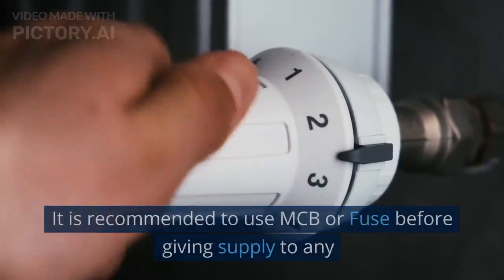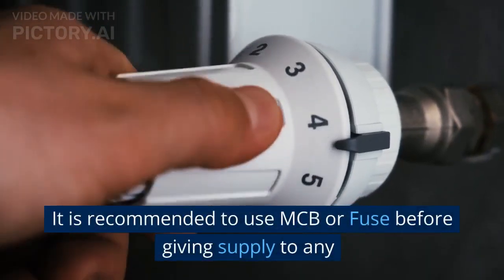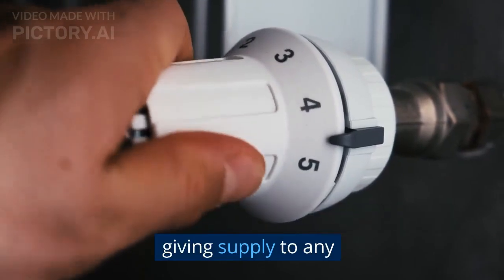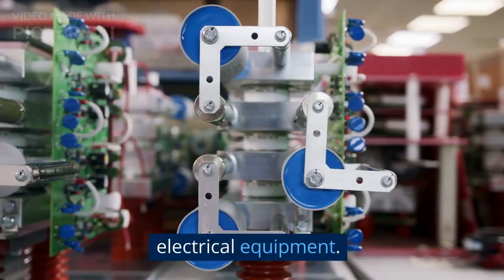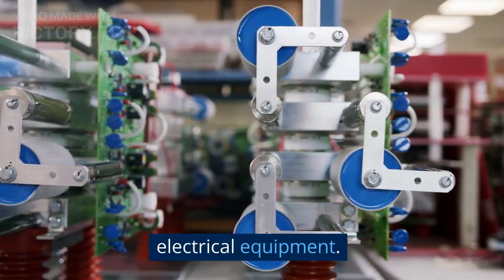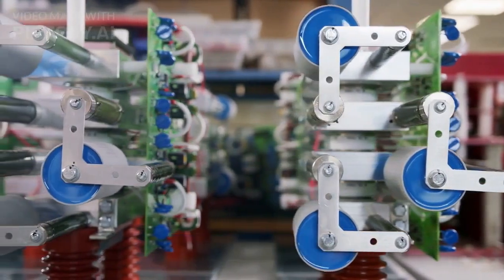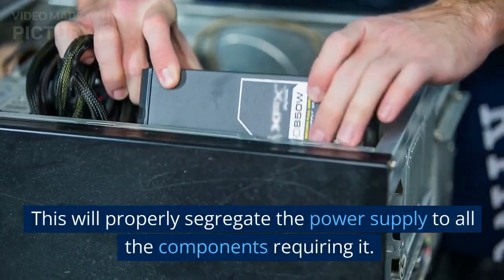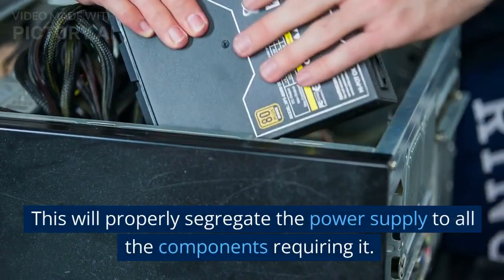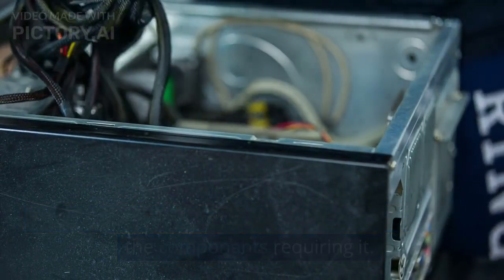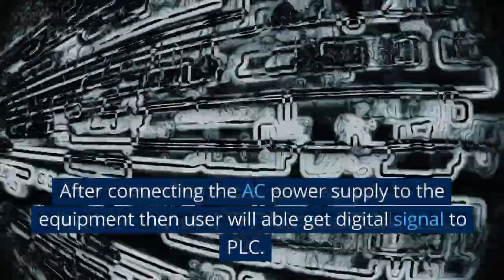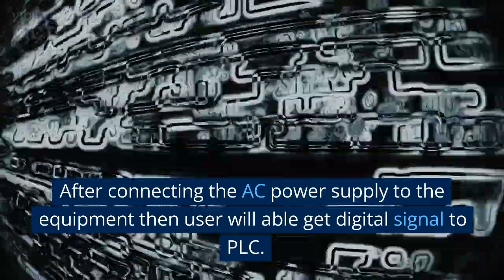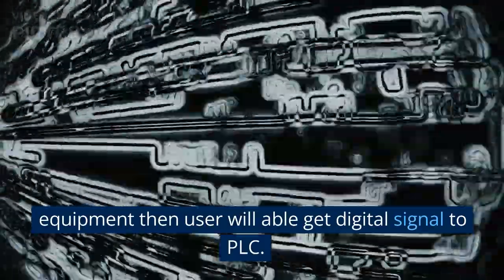First, we need a 24V DC output type SMPS for input and output connection. It is recommended to use an MCB or fuse before giving supply to any electrical equipment. This will properly segregate the power supply to all the components requiring it. After connecting the AC power supply to the equipment, the user will be able to get a digital signal to the PLC.